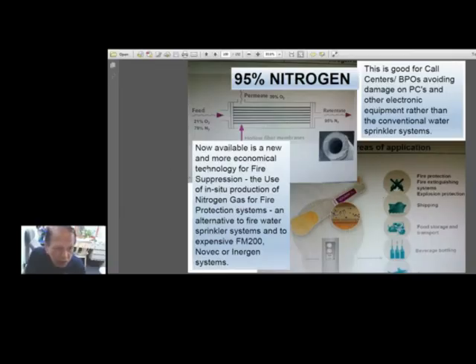Now available is the new and more economical technology for fire suppression, the use of in situ production of nitrogen gas for fire protection systems, an alternative to fire water sprinkler systems and to the expensive FM200, Novec or Inergen system. This system is fairly new. Of course, nitrogen is included in those. It is included in the Novec, included in the FM200, and included in the Inergen. But if you compare the prices of FM200, Novec, and Inergen, they are very expensive.